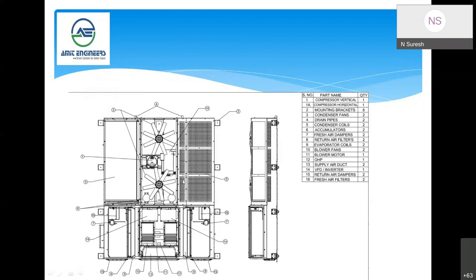And the condenser coil, as I believe, is a fin and tube condenser coil. We'll cover in the last few slides how to maintain the condenser coil to have good efficiency. There are two accumulators, one for each compressor. Basically, the accumulator is there to avoid any liquid flooding to the system.